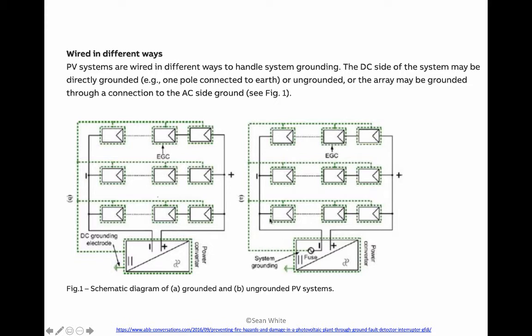So if some current was leaking out of the glass of the modules or the wire that's going along the rails, and if every module had a milliamp, a milliamp is a thousandth of an amp. So if you had 1,000 milliamps, that's an amp. So it does add up over time. For a smaller residential system, it didn't add up to anything significant, but on some bigger systems, there were actually some fires that people think were started by this type of an inverter, which is why we got to go and use these other kind of inverters right here.